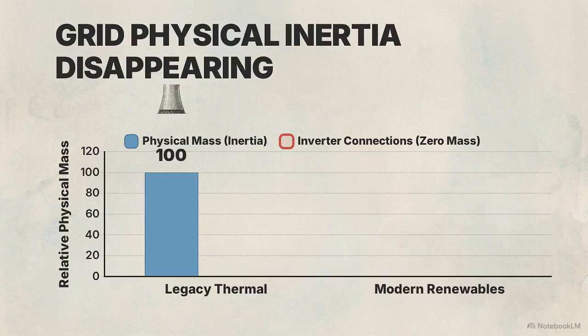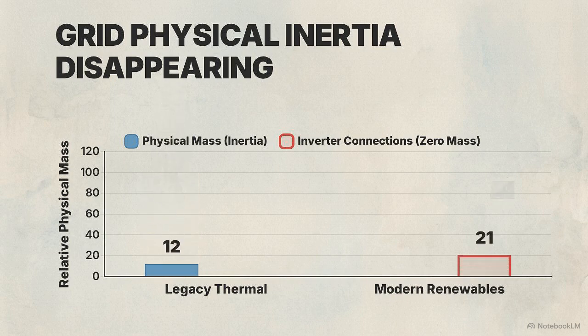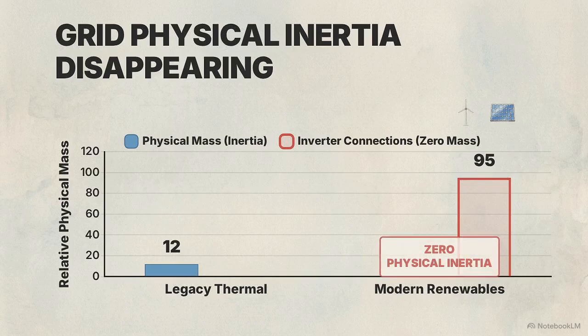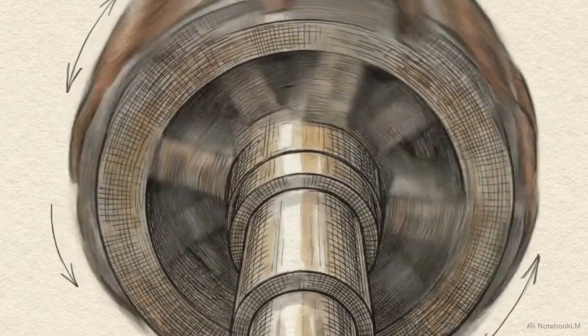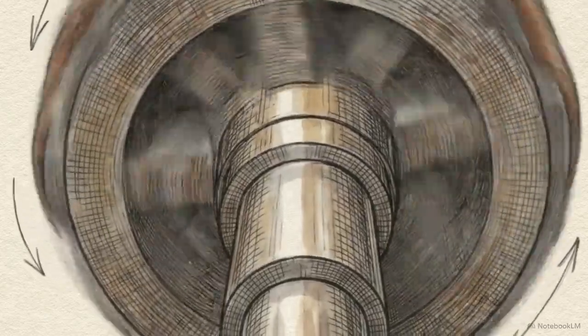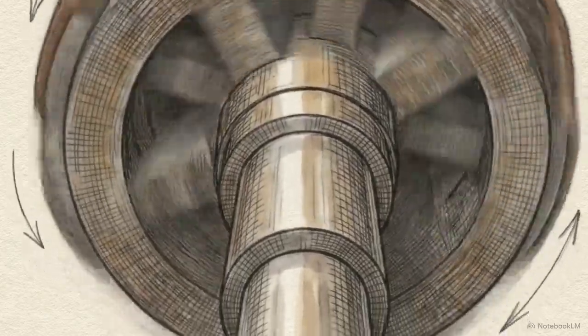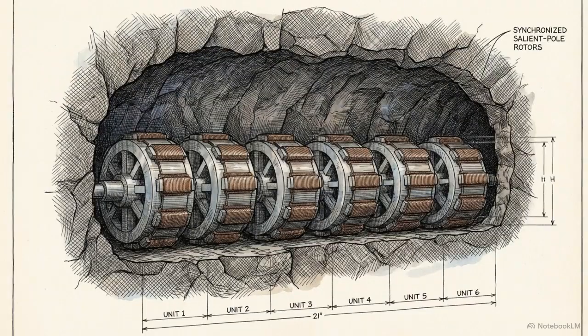This comparative chart shows a structural vulnerability in the modern grid. Heavy spinning thermal plants are retiring, replaced by solar arrays and wind turbines that connect via solid-state inverters. These renewable sources provide zero physical inertia. When grid supply and demand diverge, the rate of change of frequency accelerates. Dinorwig counters this through synchronous inertia. Its 6 synchronized 450-ton steel rotors provide a massive physical shock absorber against sudden frequency deviations.